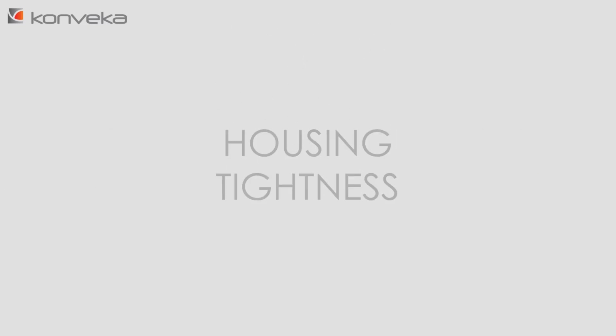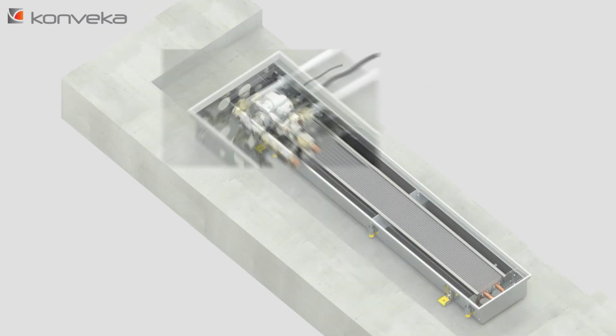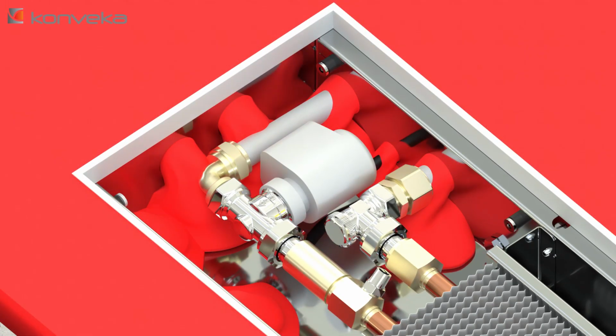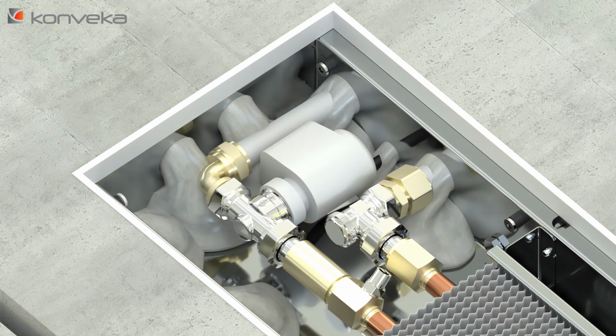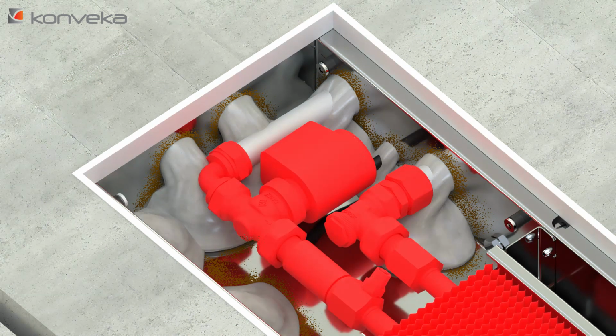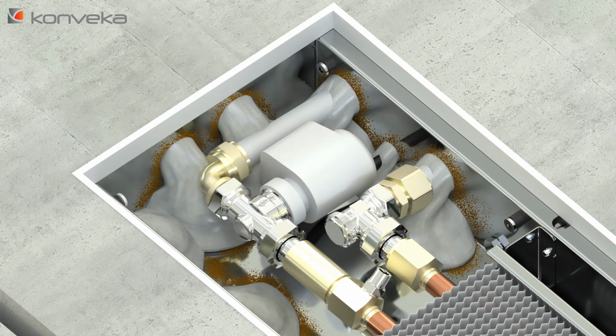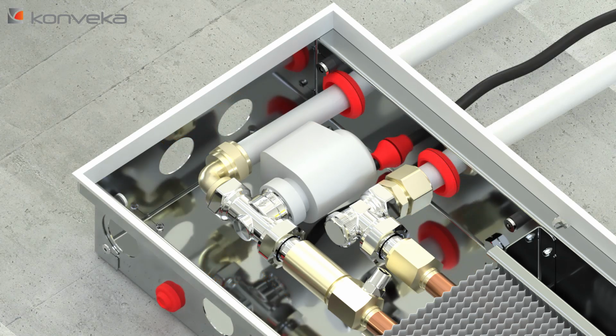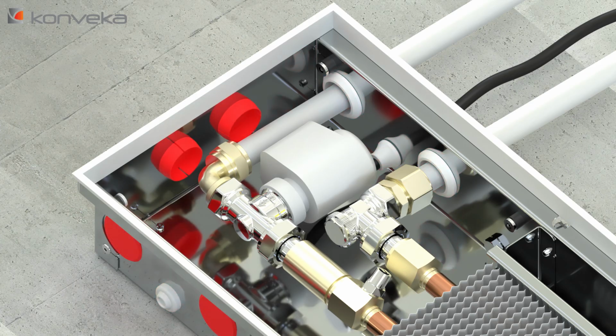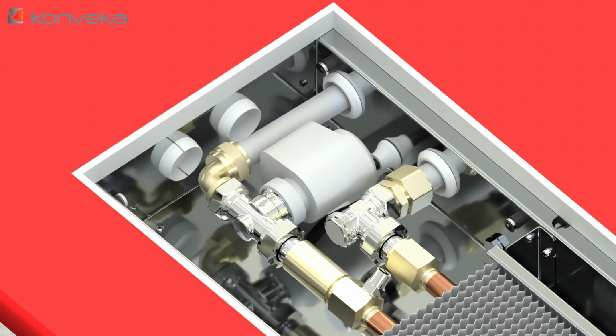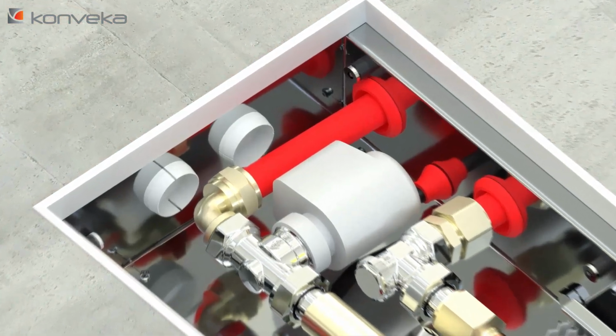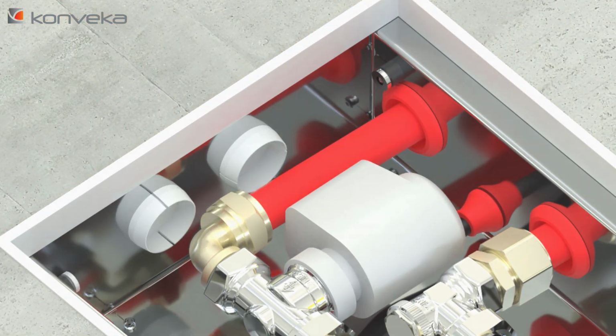Housing tightness. When pouring concrete around the convector during its installation, part of the concrete enters the inside of the housing through the openings. This compromises the visual appearance of the convector, increases the likelihood of corrosion, and may damage the parts situated inside. Removing concrete from the convector is complicated. To prevent this, we equip our convectors with sealing elements for the inlet pipes and cables, as well as with blinds for unused openings. Therefore, no concrete can enter the convector. The sealing elements also provide additional protection for the inlet pipes and cables to prevent rubbing on the edges of the housing openings.